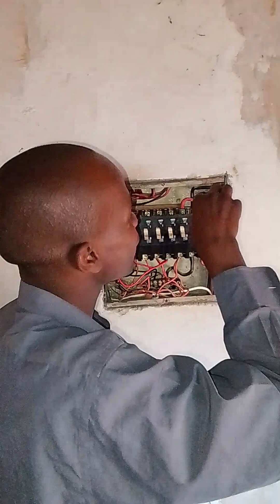And then you screw it firmly, tightly. And then also the neutral wire right here is also placed at the input. And then you screw it firmly. After this, you want to actually have connection at the loads right here. 1, 2, 3, 4, 5. These are our loads, and these are the lights. For the lights, it's the 5 amps right here. 1, 2. These are for the lights, and then for the plugs, these are for the 20 amps right here. This one and this one. These are for the plugs.